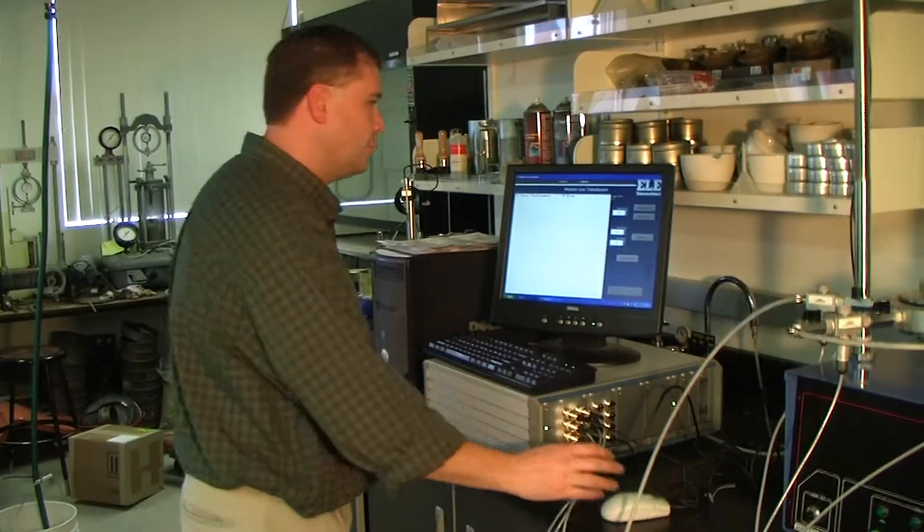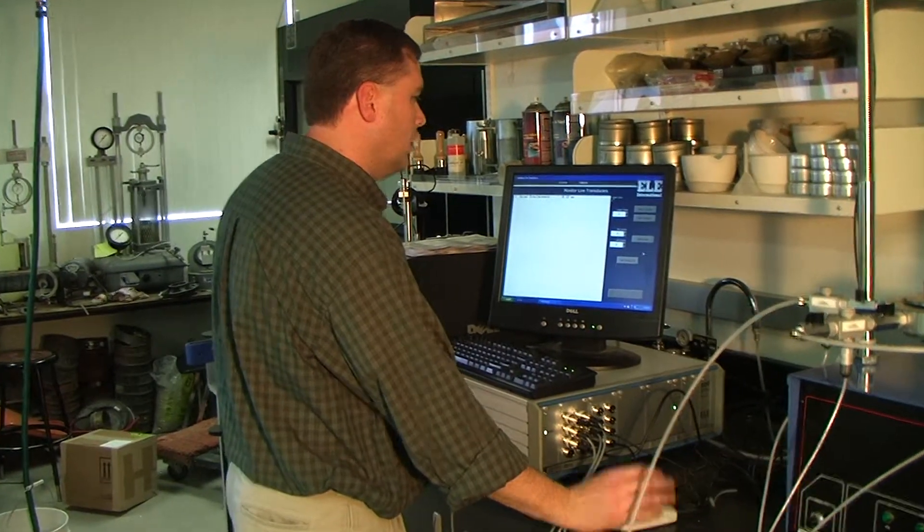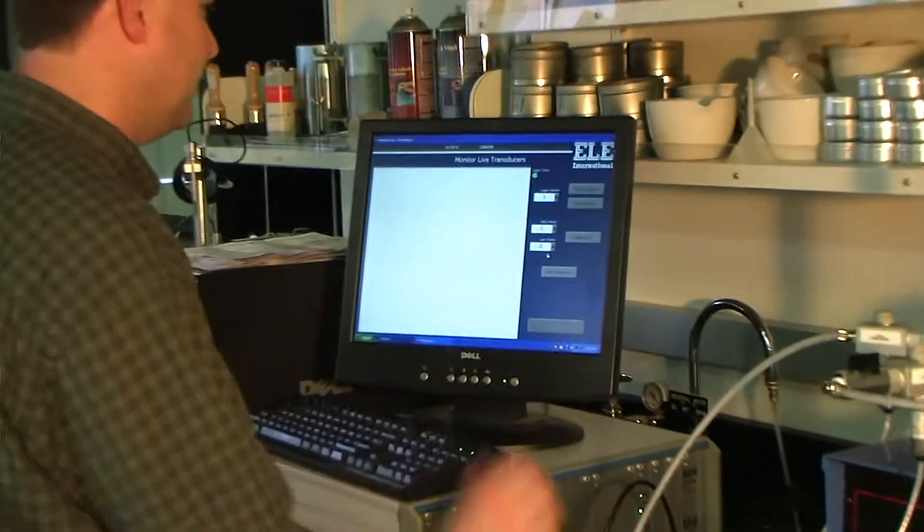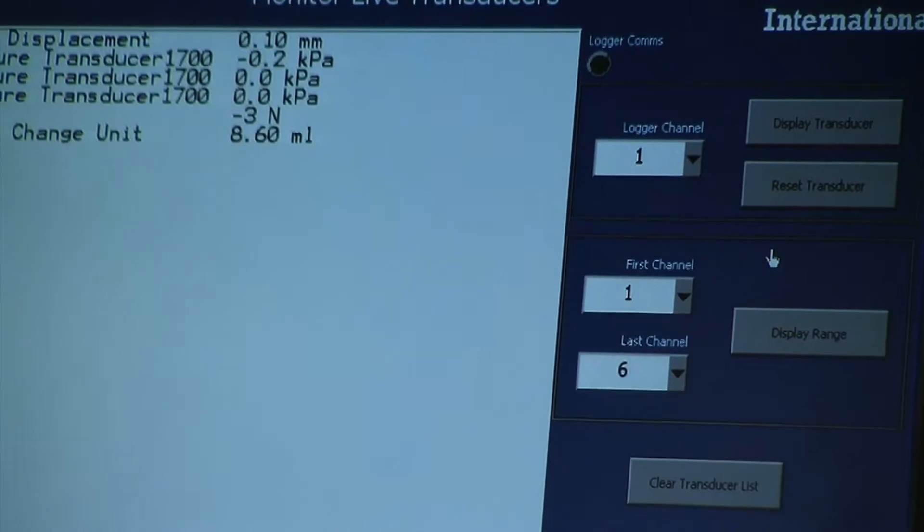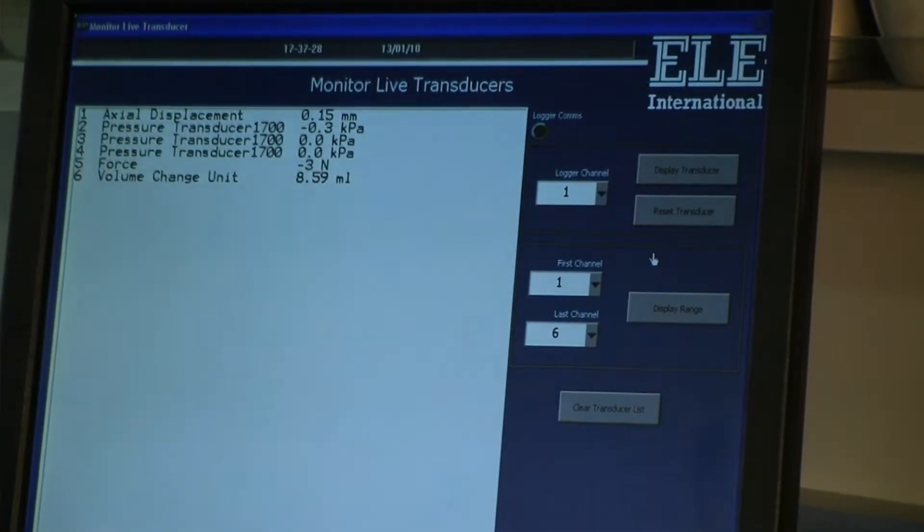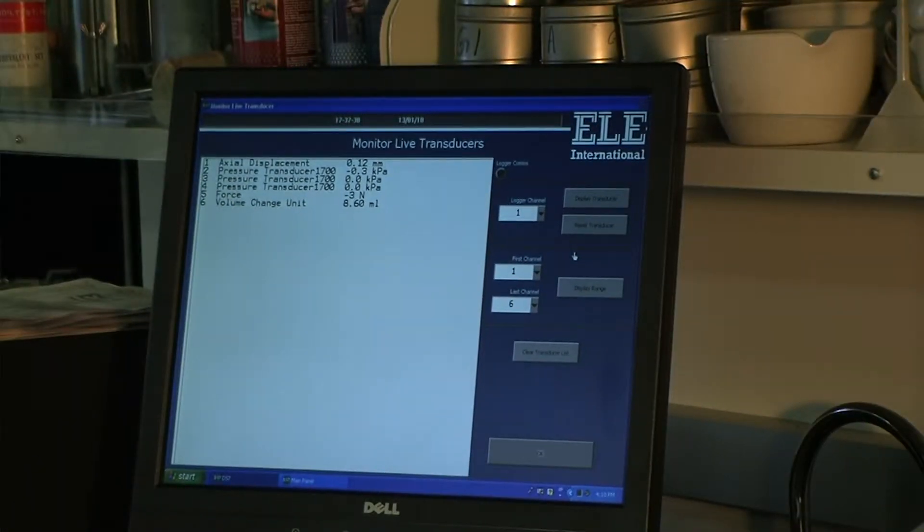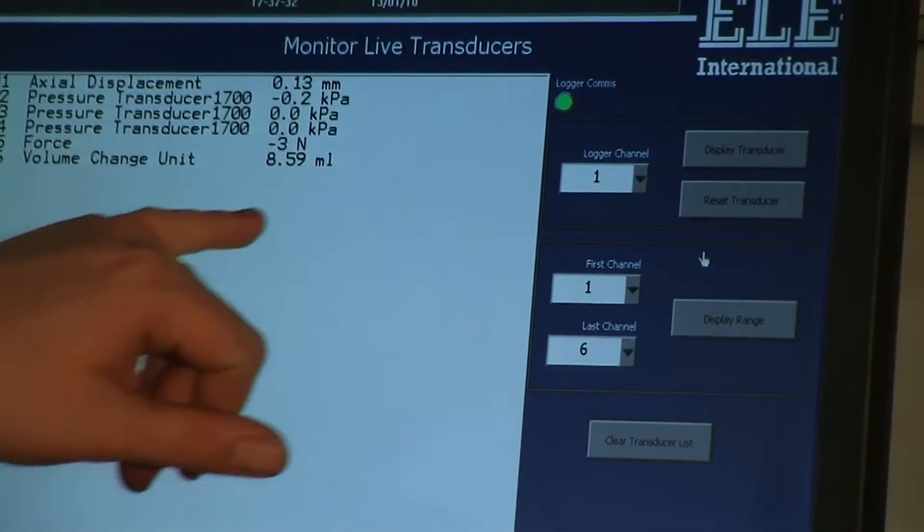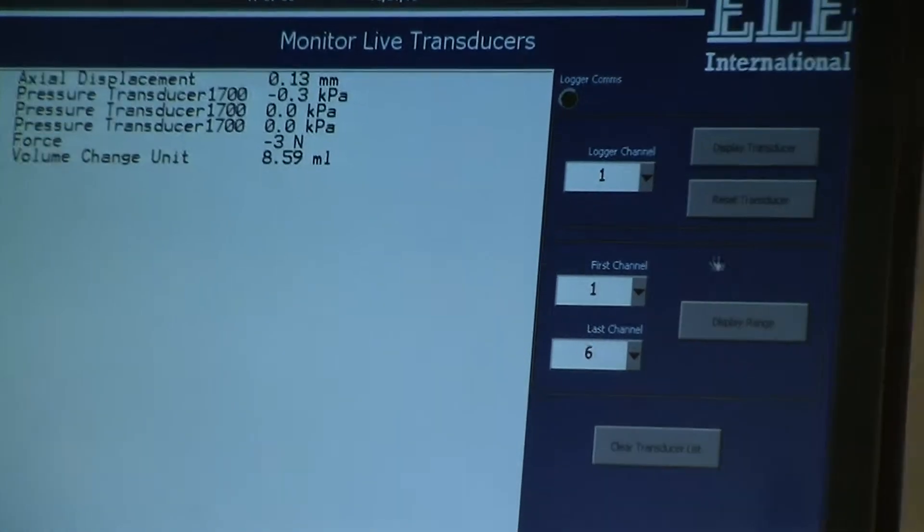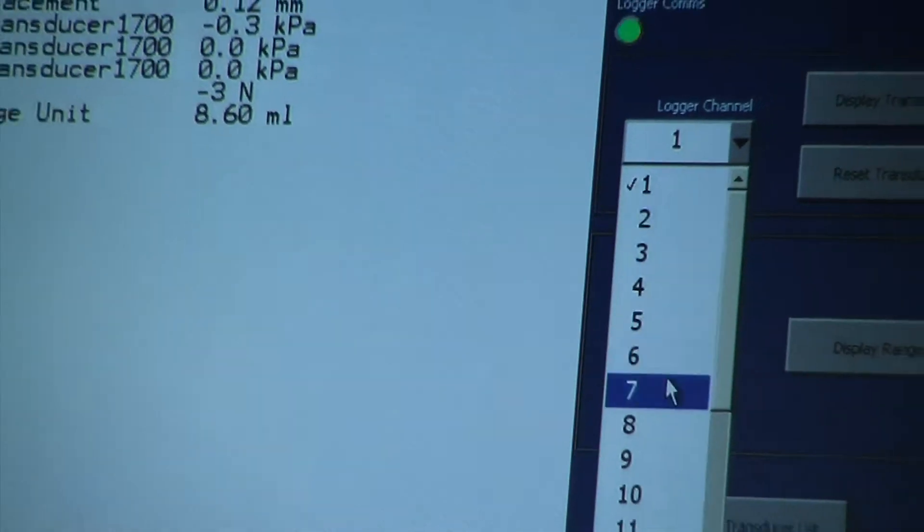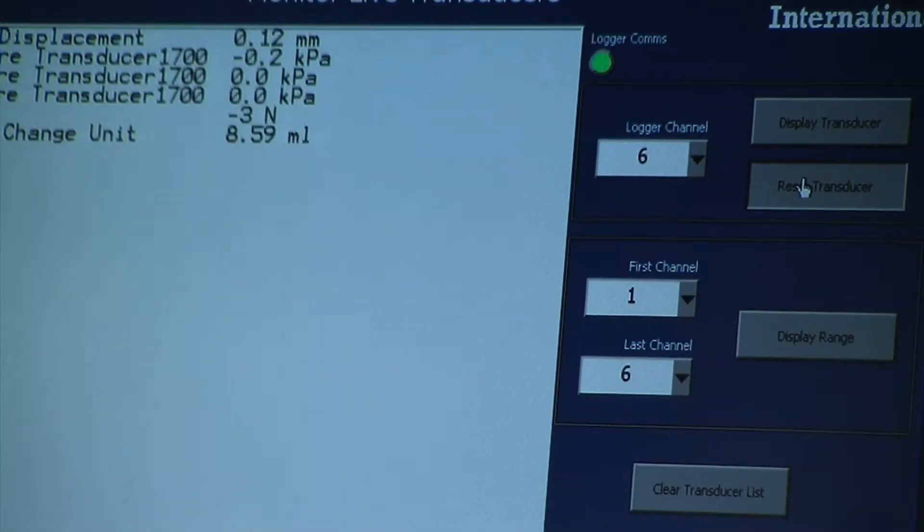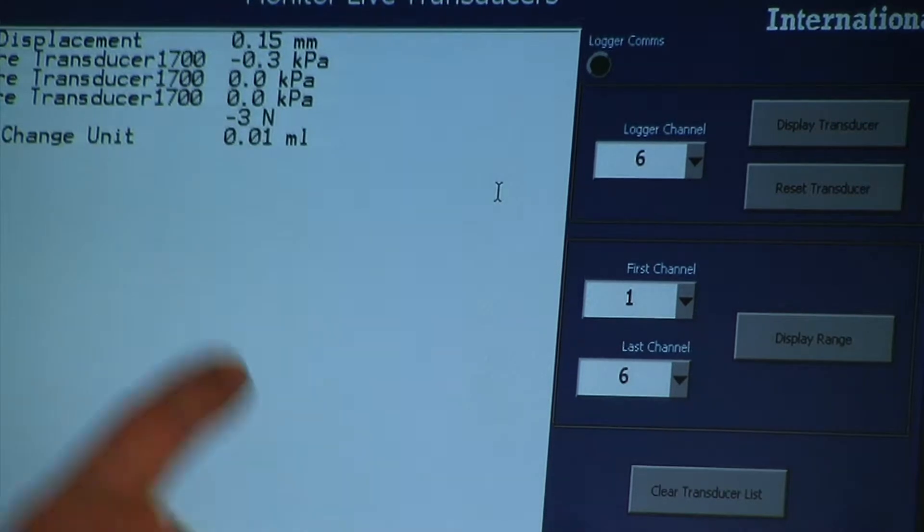Okay, now what we can do on the screen here is we can say, okay, instead of just looking, to eliminate that, we can clear the transducer list, which eliminates that. And we can look at the range. I have one through six, and I can hit the display range button. And that allows me to monitor all six transducers that I have connected in right now. And now the volume change unit is reading 8.6 milliliters. And I want to go ahead and zero that. Are you sure? And now it's back down to zero milliliters.